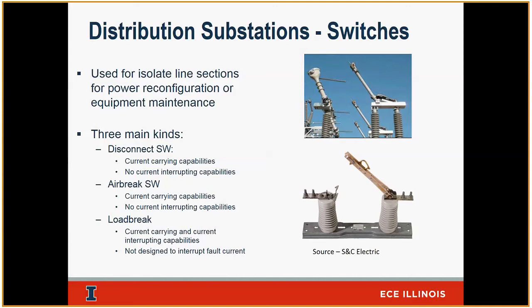The three main types of switches that we've got inside substations that Ameren are there: disconnect switches, air break switches, and load break switches. Really, the main difference between them is your current interrupting capability. So as current flows through these switches, can you interrupt current without damaging the device or not is the main concept there. And that depends on the rating of the device or of the switch. If you go to a switch yard, these are very typical switches that we use at Ameren. Both are S&C switches that you can come in and see. Manufacturers are galore for the industry. You got GE, you got Siemens, all these guys make very similar devices. But at Ameren, you can see some of that stuff easily.